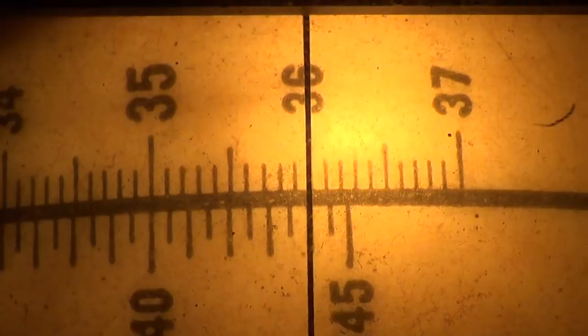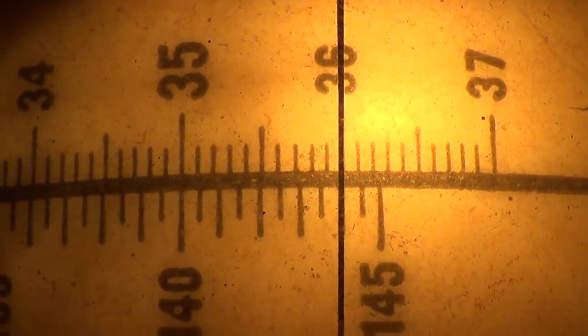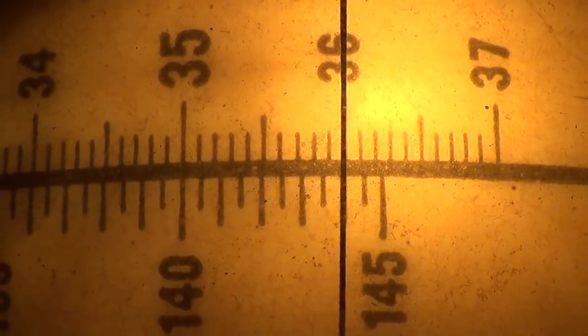Okay, I've turned the little reed on, and we're going to see if it's absolutely stationary due to the strobe light being synchronized with it and stopping its motion. We look inside here, and the little reed is wiggling a bit. So that means we've got to adjust on the side with our screwdriver. I'm going to use my trusty screwdriver in the adjustment screw on the side. Isn't that weird? It looks like it's just barely moving back and forth, and it's going 3,600 vibrations per minute. Let me see if I can slow it down any. There we go. I think that's pretty close. There it is. I think it stopped. Okay, we're calibrated.